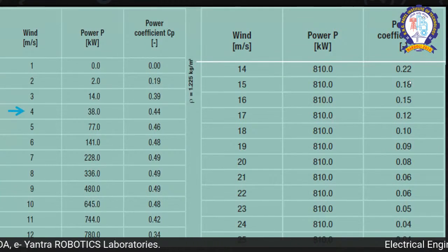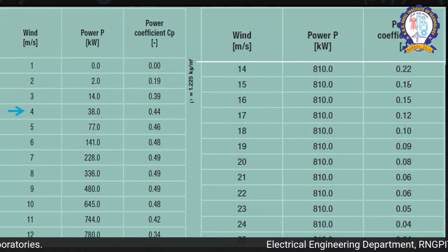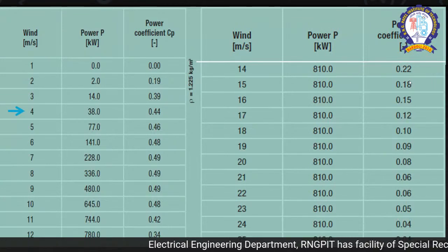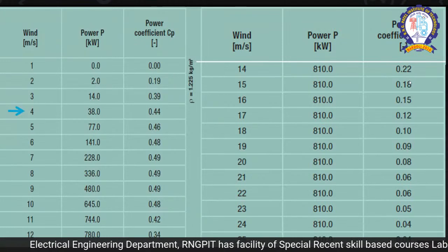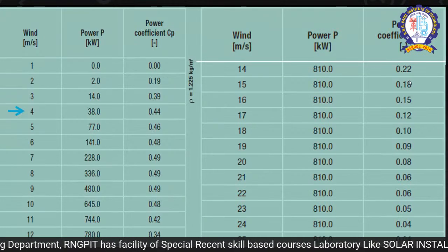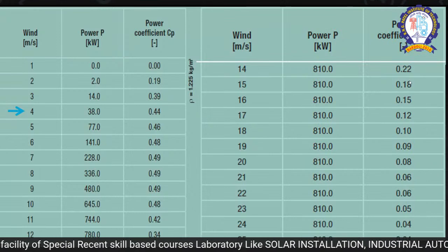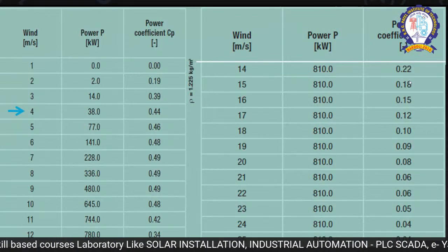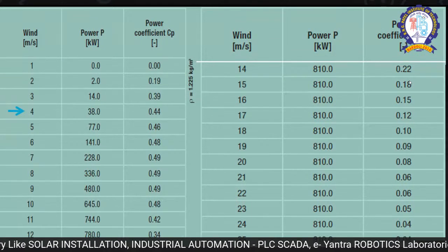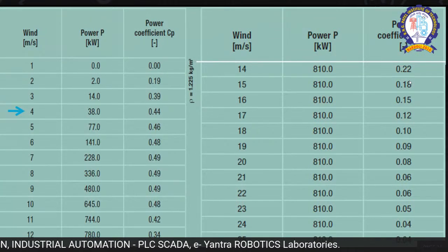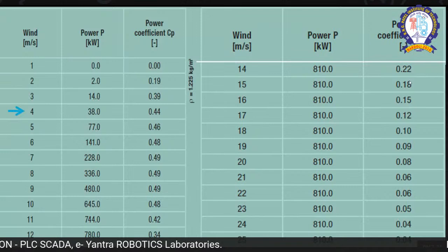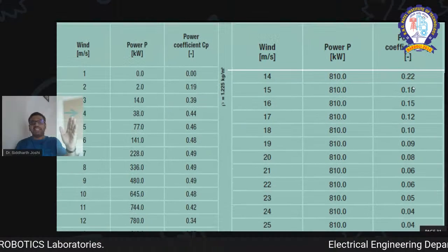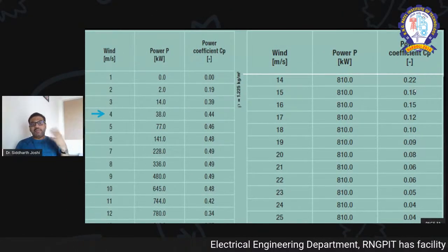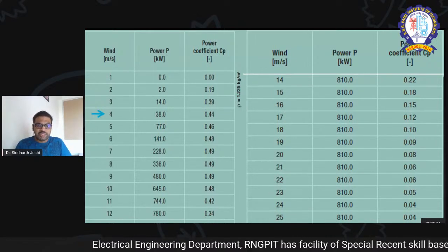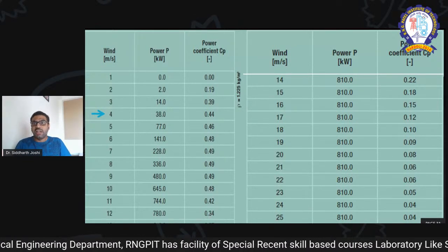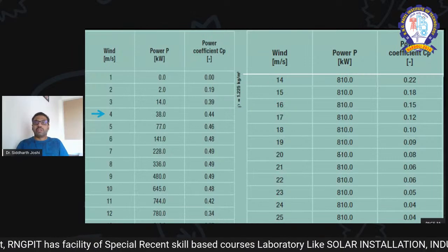higher, because as per the equation, it is half rho A CP V cubed. Then power is proportional to V cubed, and your generator might be burned out because you are working above the capacity of the generator. So after this 12 meters per second of the rated wind speed, there is pitching of the turbine. Are you getting me? There is pitching of the wind turbine by sacrificing the value of the aerodynamic efficiency, CP or power coefficient, and maintaining electrical power output constant.